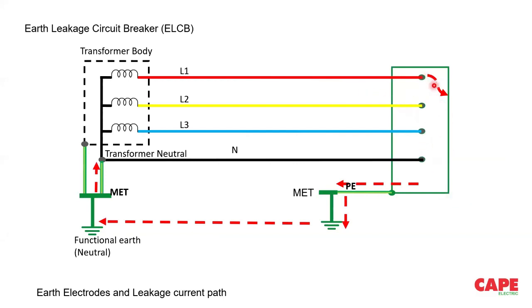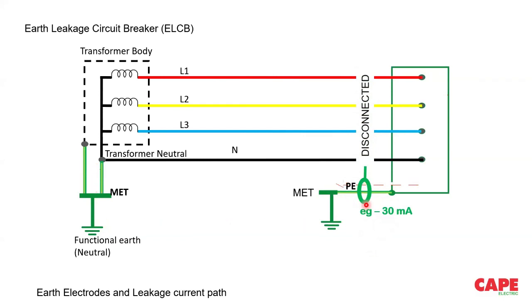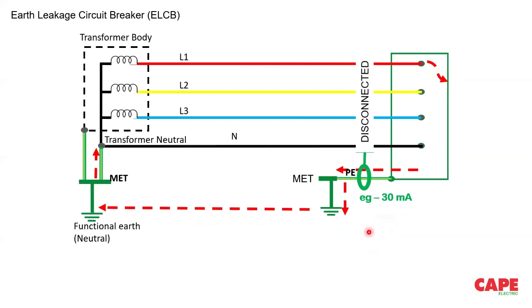Now I am showing you a TT network. There is a fault, and the fault current is going through the earth electrode, and it is circulating in this circuit. Now ELCB is a device which measures the current flowing through this earth wire or this protective conductor. So there is a conductor which is carrying the leakage current, and the leakage current is measured, and a mechanical device is connected which will disconnect in case of a leakage current more than its set current, say for example 30 milliampere. So ELCB works by the principle of measuring the current through a wire. This device disconnects in case of a current higher than 30 milliampere, and your installation will become safe.